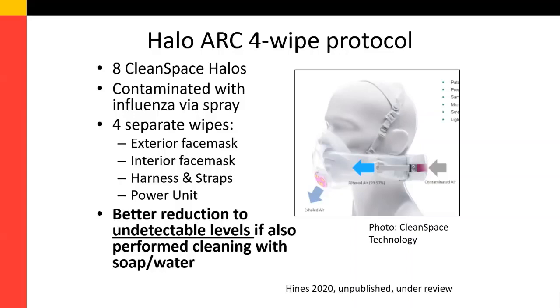The wipe process was a 4 separate wipe protocol where 1 wipe was used to cover the entire exterior surface of the face mask. A second wipe was used to clean the interior surface of the face mask. A third wipe was used to clean the harness and the straps, and then a 4th wipe was used to clean the power unit.